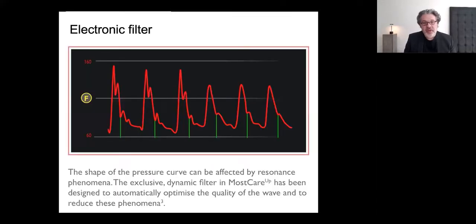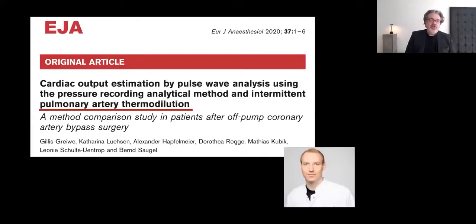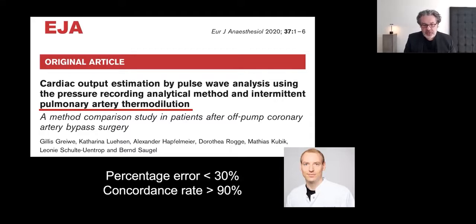So this electronic filter is, I think, pretty interesting. It is possible today to automatically correct an underdamped arterial pressure waveform and thereby improve the accuracy of pulse contour methods. In fact, there's already one study published where they used this electronic filter to monitor cardiac output in patients in whom the arterial pressure waveform was underdamped. It's a study from the group of Bernd Saugel that was published two years ago in the European Journal of Anesthesiology, comparing it with pulmonary artery thermodilution measurements. They reported a pretty low percentage error and a pretty high concordance rate, which is honestly pretty uncommon for most pulse contour techniques.